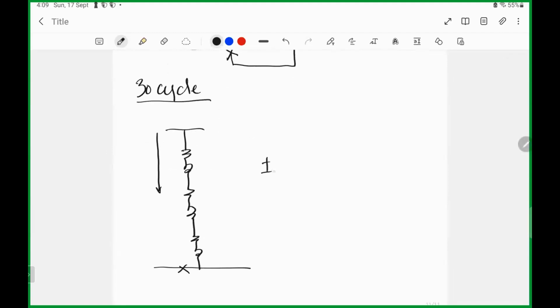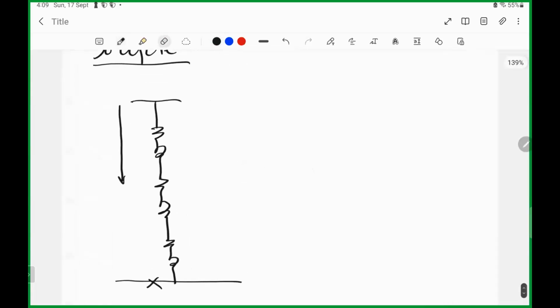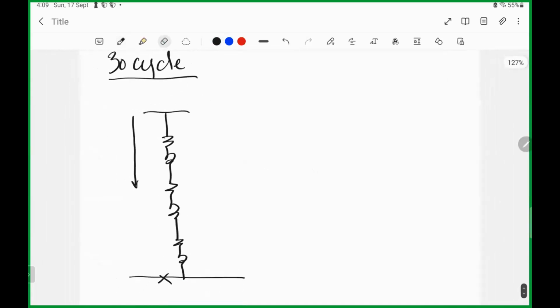So the I fault three phase here. You can also check this one, meron na ako. Ay sorry, not I three phase, sorry. I fault line to line. Sorry. Nahilo na class. I fault 3-phase nga. I fault 3-phase at 30 cycle. Lagay natin. So, MVA base divided by square root of 3 times 400 volts.